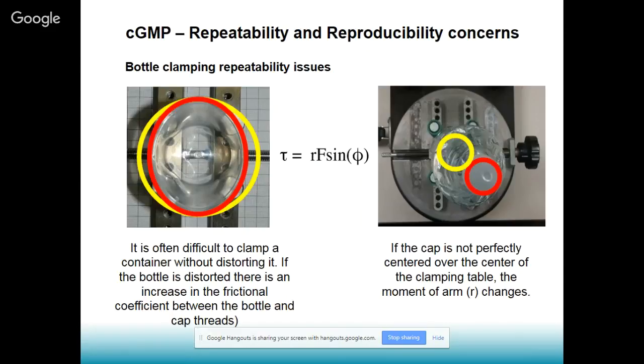And in the next slide, I wanted to show a repeatability and reproducibility problem as far as the manual clamping. Some torque testers have this clamping mechanism where you clamp the bottle at the bottom, and there's nothing wrong with it as long as, again, the operators understand how to set these clamping fingers up properly and how to test the system properly. But I wanted you to be aware that if you distort the bottle, or if you throw the center of the rotation off the center of the clamping platform, that will introduce some torque errors in the measurement.